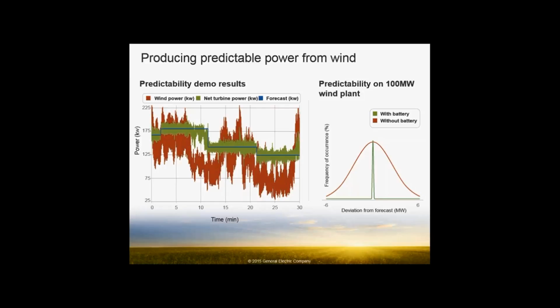What we're learning is that we can create, in effect, a buffer capacity to make the wind more predictable for, say, a 10, 15, or 30-minute period. We have the ability to commit power for different time periods and close down the standard deviation compared to without those plant controls. On the right, you're seeing a deviation of plus or minus 6 to a mean - with batteries, we can effectively close that for specified periods.